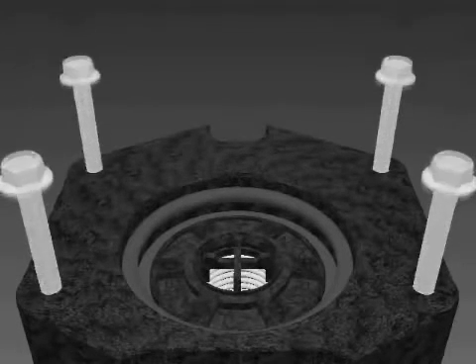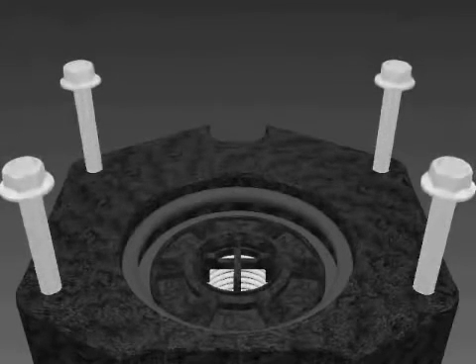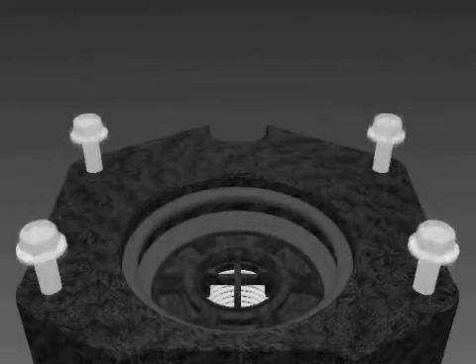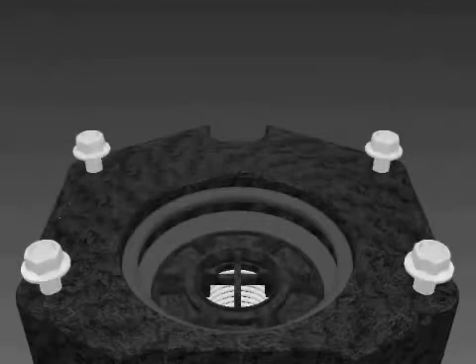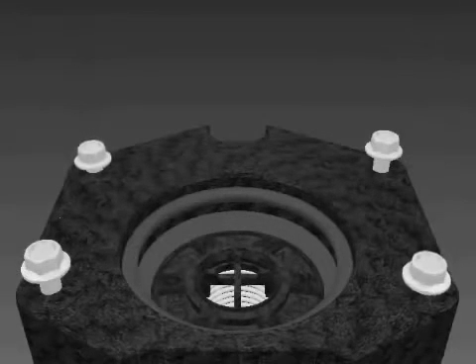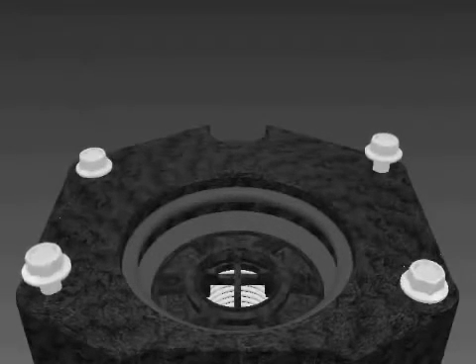Place the cartridge assembly into the cover. You will center the flange on the diaphragm and line up the bolt holes with the cover. Next, you will drop the four bolts into the cover. Push down on the seat of the cartridge with a thumb until it bottoms in the cover to align the diaphragm holes. Then tighten two opposite bolts. Release the seat and tighten the two remaining bolts.